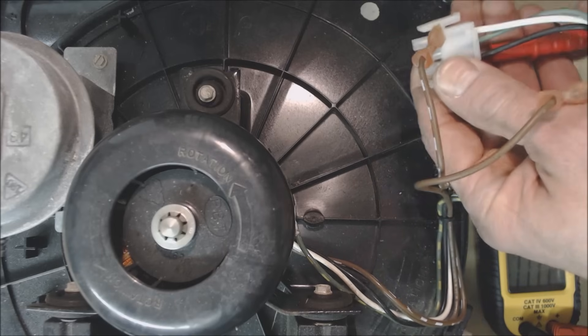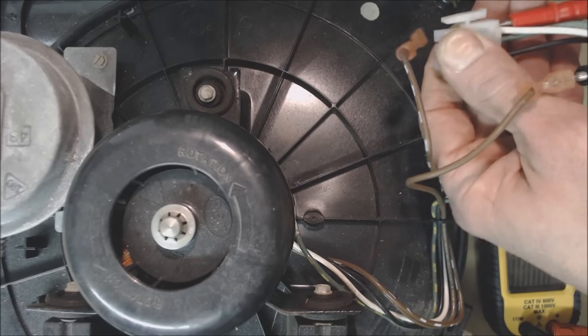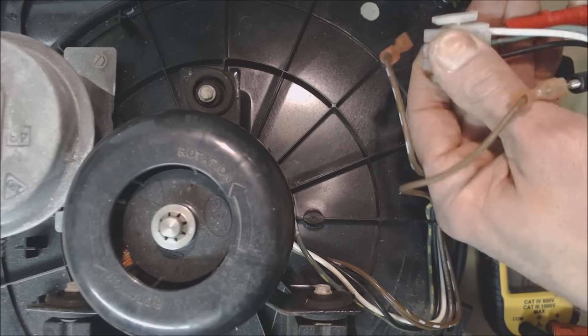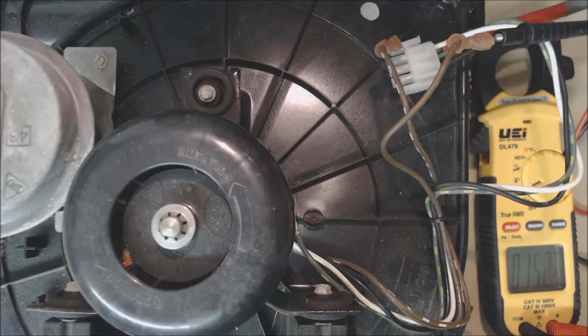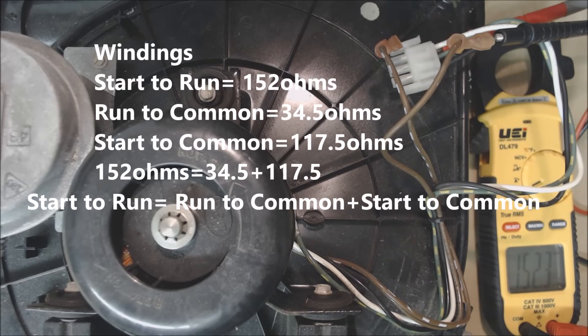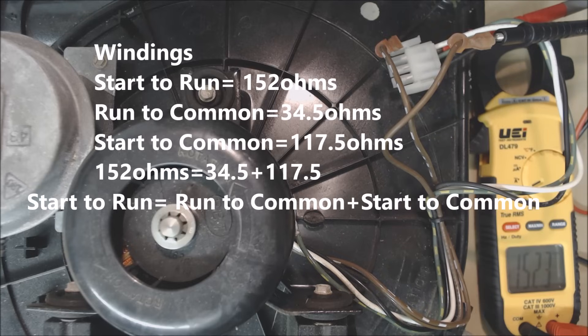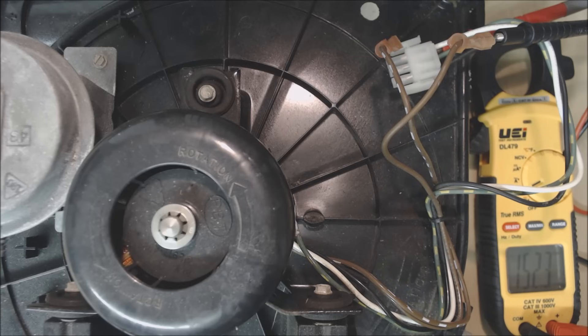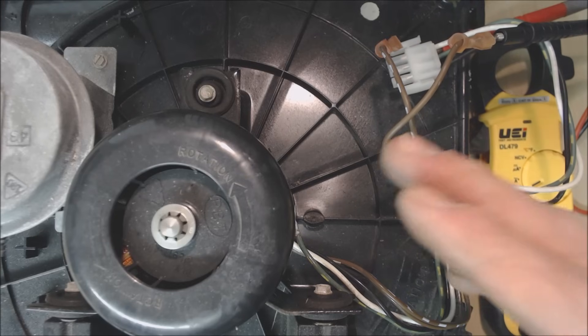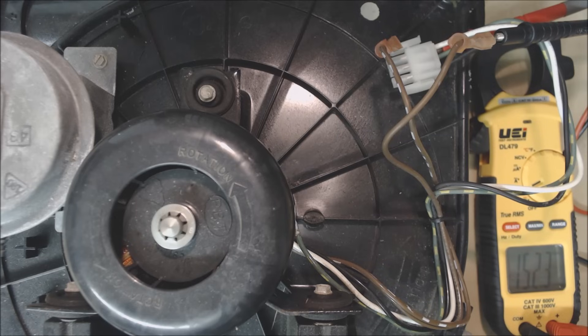And now we'll go ahead and check from common to hot. Basically what we're making sure of is that we don't have 0.0 ohms of resistance and that we don't have OL because OL would mean that the windings are burnt apart. And 0.0 ohms would mean that the windings are all melted together. And you see that we have 152.3 ohms. So this motor checks out good in reference to the resistance readings.